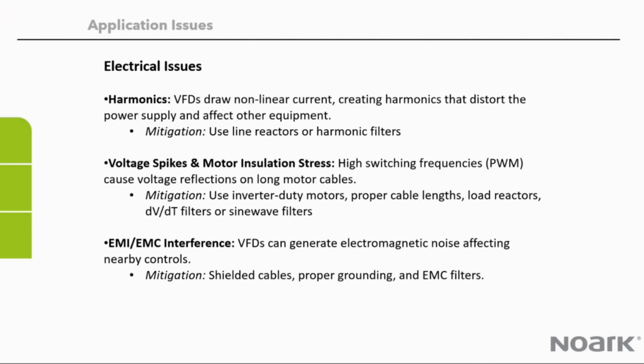Things to be considering, common issues you may encounter: harmonics, voltage spikes, and electromagnetic interference. In harmonics, VFDs draw nonlinear current. They could potentially cause harmonics that distort the power supply and affect other equipment. A common method to overcome this would be using line reactors or harmonic filters.